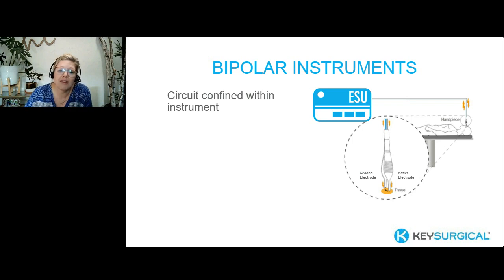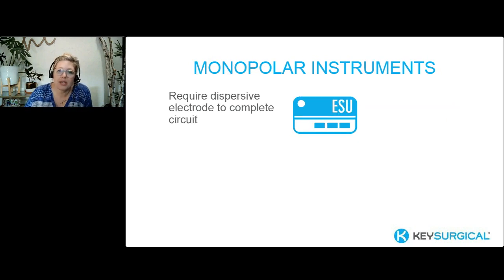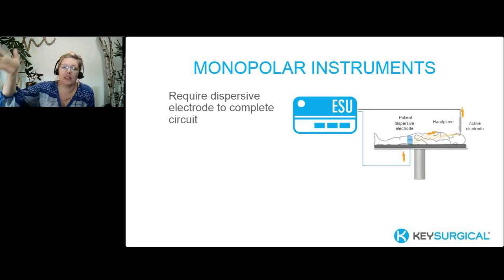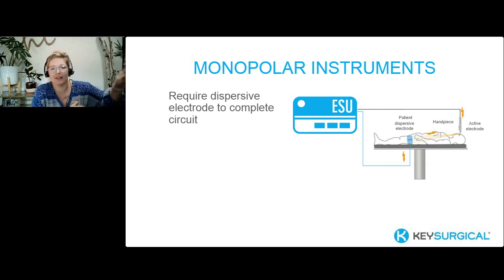And contrary to that, we have monopolar instruments. So these are those instruments that require a dispersive electrode. If you think about it in this way, that's why we need that dispersive electrode. We need to create a safe area for that circuit to exit the body and return to complete the circuit. So here we have the active electrode still being our instrument, and that dispersive or return electrode now becomes that pad that's plugged back into the ESU.